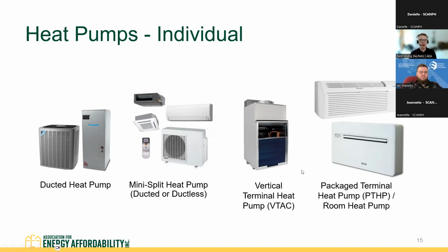Another option you may come across, particularly in new construction, is something called a vertical terminal heat pump. It's like something in between a package terminal heat pump, or PTAC, and a ducted heat pump. It's attached to an exterior wall, similar to a package terminal heat pump, but it has ductwork that generally goes up and sometimes can go over to the side, maybe to an adjacent bedroom or two. These are moderately efficient—not great, but they work, about as efficient as a package terminal heat pump—but they can be relatively low cost, so this is an option we're starting to see folks go with.